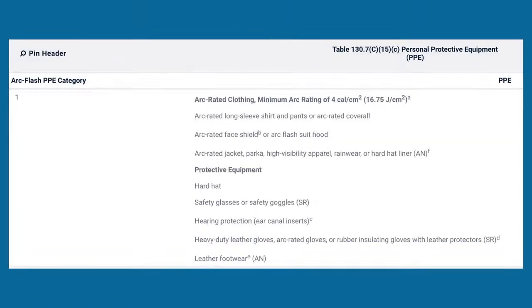All right? Now, I like it. Look at this. If I'm in hazard risk category 1, this is an arc rating up to what? 4 cal. They're going to tell you here, all I have to wear is safety glasses or safety goggles. You don't see a face shield. You see that? Now, if I'm looking up above it, that's just protective equipment. Now look up. It says an arc rated face shield or what? A suit hood. A lot of people will go down and look at the protective equipment and won't look at the arc rated stuff here. Even at up to 4 cal, I have to wear what? A face shield.